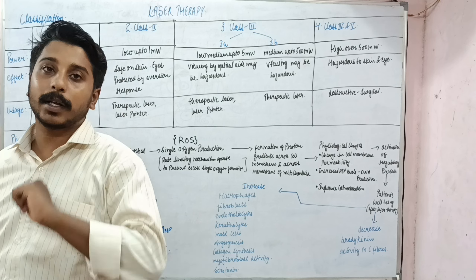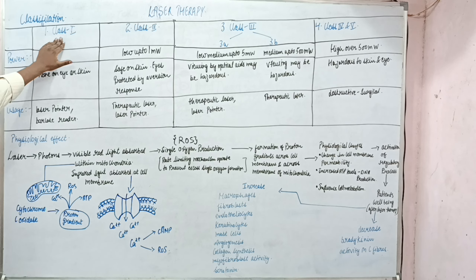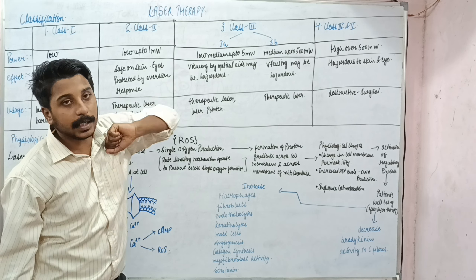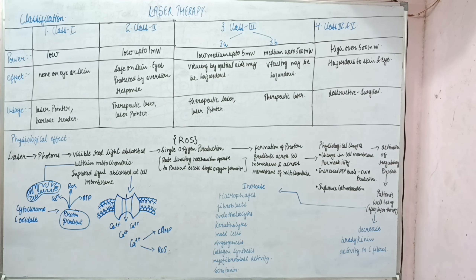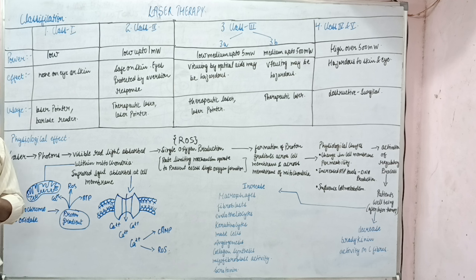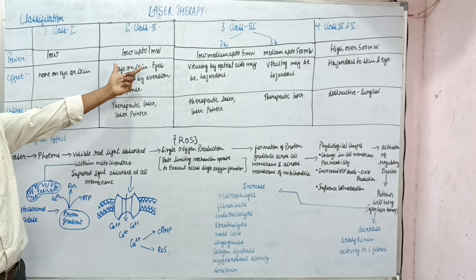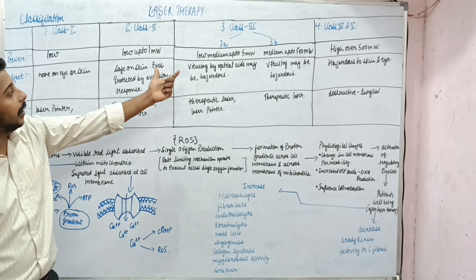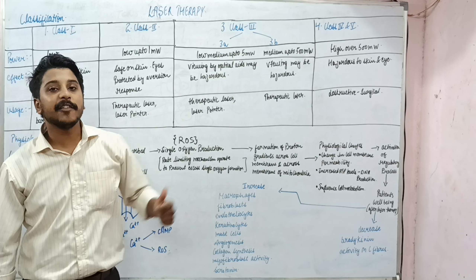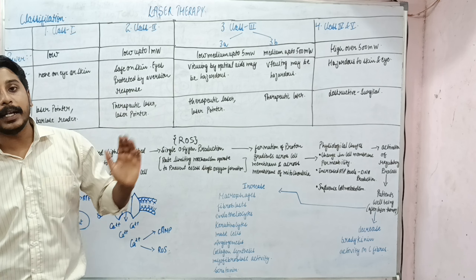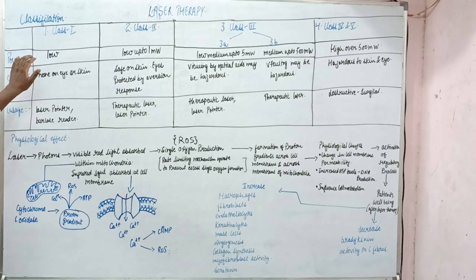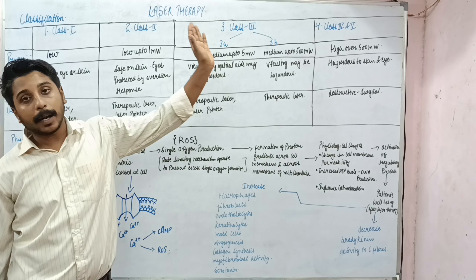Under the classification, laser is classified into four classes — more appropriately five classes. Class 1, Class 2, Class 3, with Class 3 further divided into 3a and 3b, and lastly Class 4 and 5. Regarding power: Class 1 is very low power, Class 2 is low up to 1 milliwatt, Class 3a is low-medium up to 5 milliwatt, Class 3b is up to 500 milliwatt, and Class 4 and 5 are greater than 500 milliwatt.